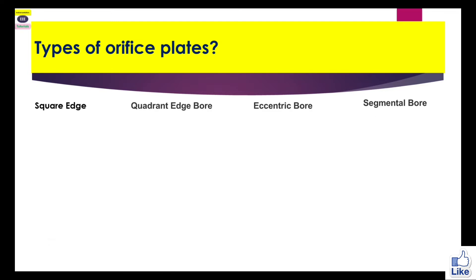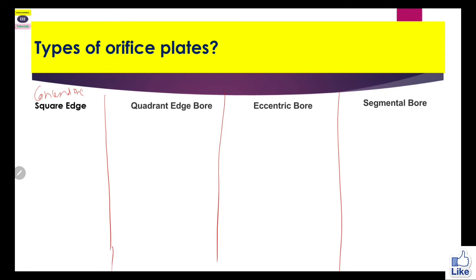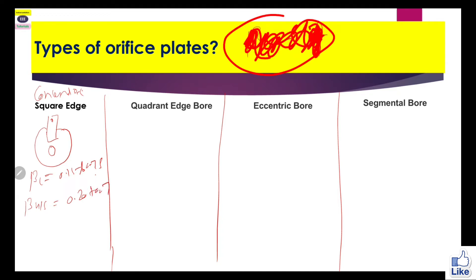Our next point is types of orifice plate. Generally there are four types: concentric square edge, quadrant edge, eccentric bore, and segmental. The concentric square edge is the most used orifice in the oil and gas sector in instrumentation and automation. The beta ratio for liquid is 0.15 to 0.75, and for gas or steam it is 0.20 to 0.70. The beta ratio should be maintained below 0.75 to get accurate flow measurement from the orifice.